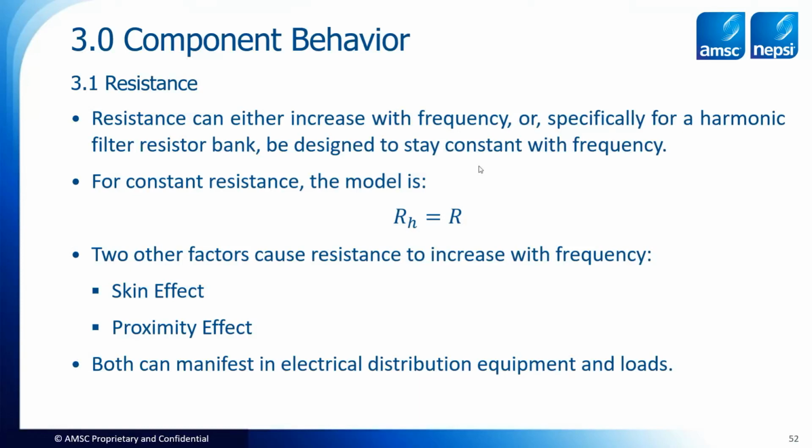There's a lot, I'm going to just barely touch the top of this. There's a lot of details. I've seen some really good papers written on using finite element analysis that show how this works and affects the resistance and the equivalent value. But let's just touch on this, okay? So we have these two key effects, skin and proximity effect, and both can manifest in electrical distribution equipment and loads, and more importantly, in our harmonic simulation work.